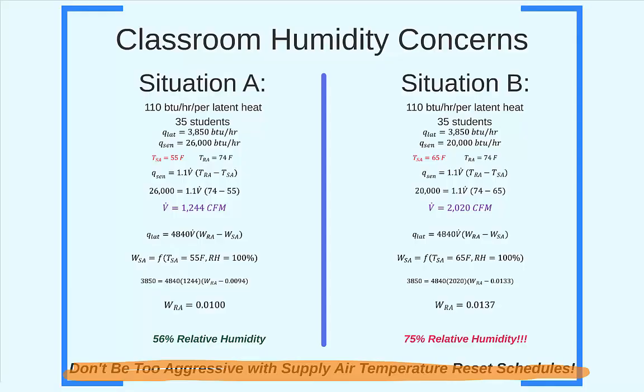Additionally, in the example we just saw, the CFM of the air increased from 1244 to 2020 CFM. That 62% increase in airflow would result in an increase in fan power requirements associated with this space.